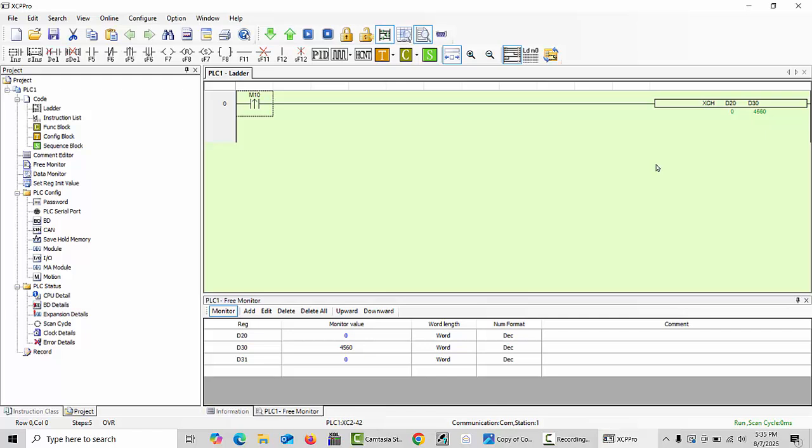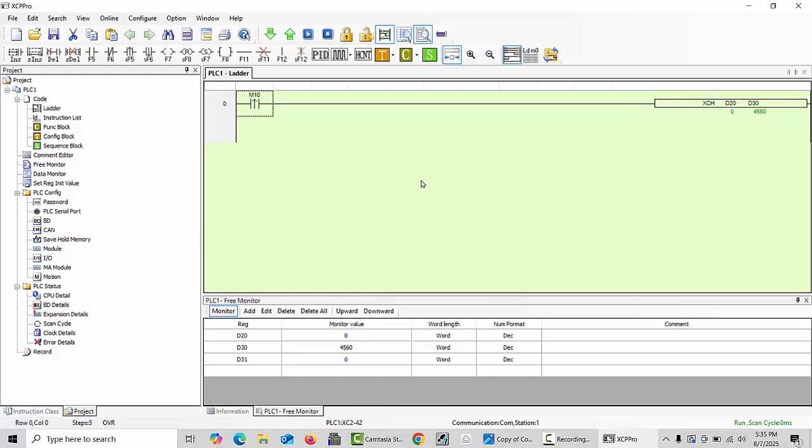Important notes I can share with you: the XCH command can be used with most data registers, meaning D registers. Both operands must be of the same data type. The operation is performed in one scan cycle. You can use this in ladder logic or instruction list programming. Some XINJE PLC models may have slight variations in syntax.